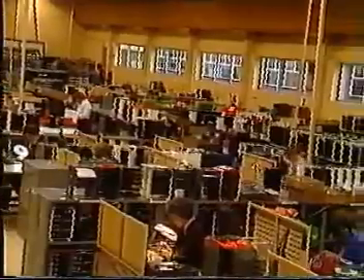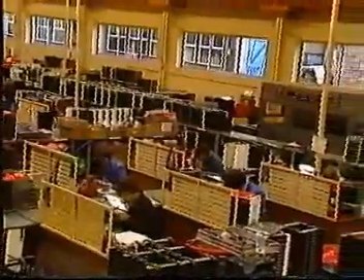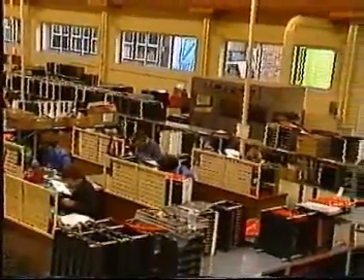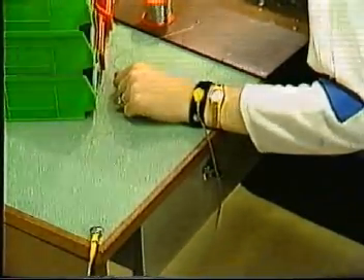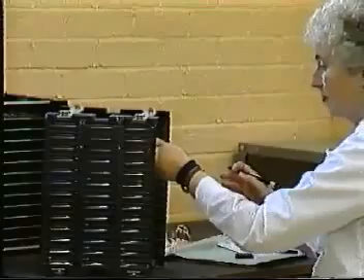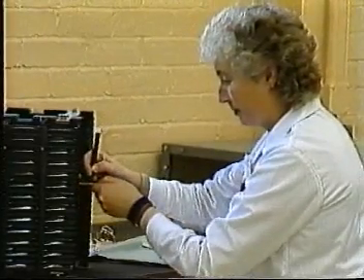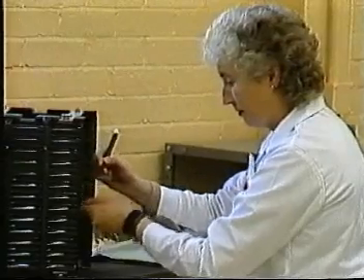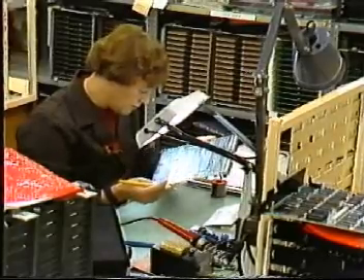The manufacturing area for the GEM80 microprocessor control system is, in its basic design, totally compatible to the handling and the assembly of static sensitive devices. This floor, for example, is static conductive. All benches in the area have been designed to be static conductive. And on all occasions where static sensitive devices are handled, the operator wears a carbon impregnated wrist strap. The aim? To maintain a condition of zero potential between any operator and any static device throughout the complete manufacturing cycle. No electrical charge or discharge can occur between the operator and the component.